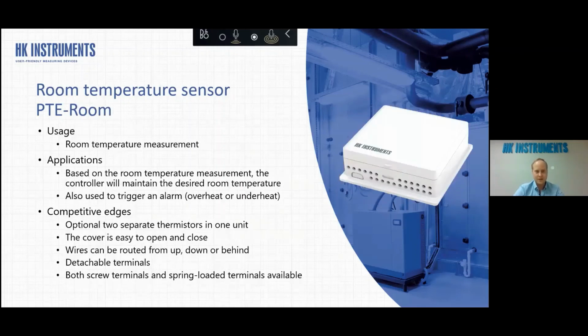Then we have these room sensors. So this is very basic sensor, for the room temperature measurement, so that you will be having a desired room temperature. And we have optional to implement 2 different thermistors in one unit. So if you don't know if the project is having PT1000 or NTC10K, you can have this with both of those, and based on the building or the system, you can use it either way. And the cover is very easy to open, and you can bring the wires from different sides easily. And this one has also these detachable terminals.